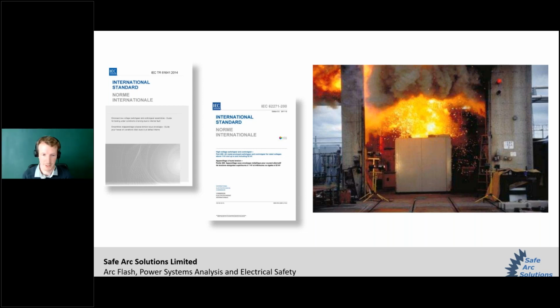A good example of arc resistant switchgear is shown on the right under test. The switchboard is in the center, and if someone's standing in front of it on the left-hand side operating it and an arc flash occurs, the design is such that the energy, arc flash vapors, flames, and heat are sent upwards and away from that person. Although this isn't going to be a nice experience to be standing there, it's better than having the arc flash directed straight at your face and chest, as we saw in the earlier videos.